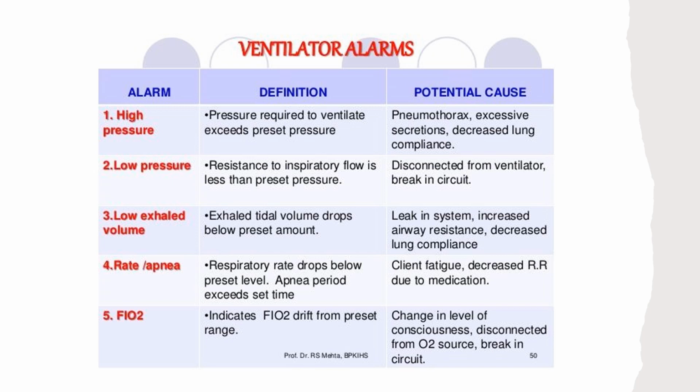And then if we have FiO2 alarms, this indicates an FiO2 drift from the preset range. So again, this can be changes in the level of consciousness. There can be a disconnect from the oxygen source or a break in the circuit.